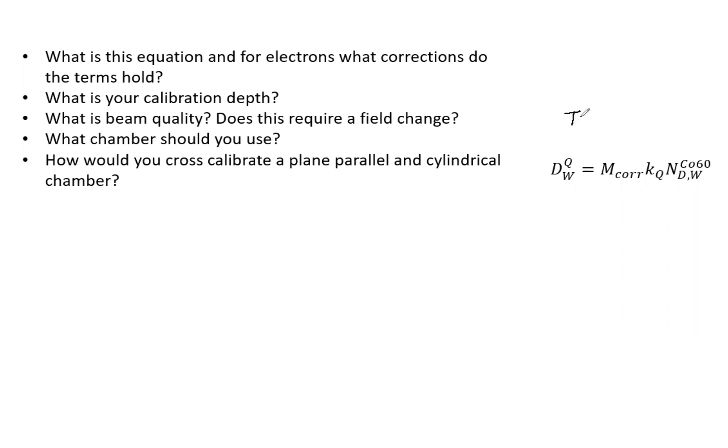First of all, hopefully you recognize it. This is TG-51. This is ultimately going to give you the dose to water for electrons. We have our gas chamber taking measurements in water at a certain depth, but we want the dose to the water as though your chamber weren't there. That's ultimately what we're trying to do.